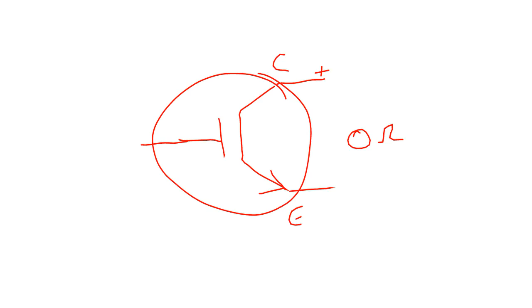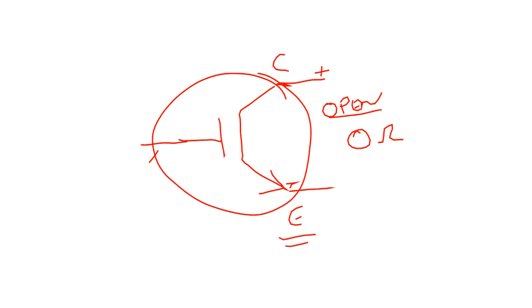So you should look at the IGBT and look for signs of physical damage, and then what you'll see is an open, very high open in both directions. Some people say that you can send a signal using a Fluke on the gate of the IGBT, and then you can monitor the collector emitter and see if it opens and closes. Yeah, it can, but in truth, it's not pulling high current, so that's not proving that the IGBT is good. So for IGBTs, it's a bit more difficult, but for SCRs and diodes, pretty much 99.9% of the time, they fail short.